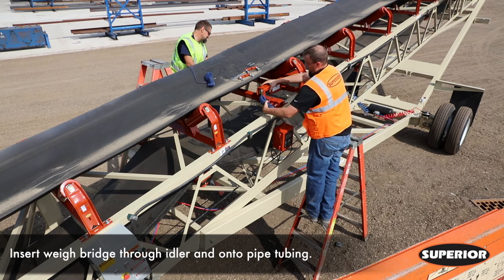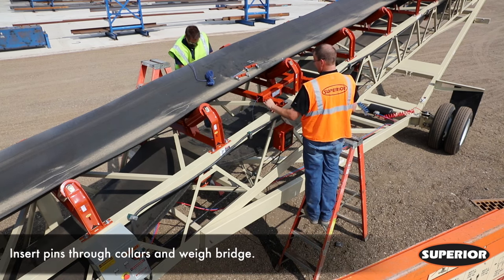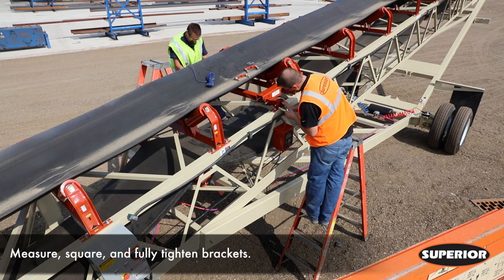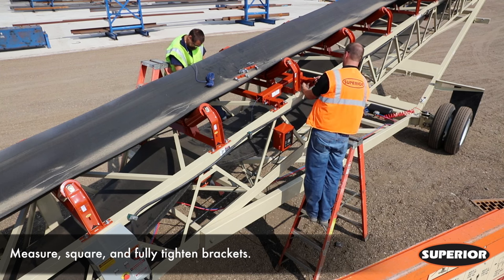Insert the weigh bridge through the center idler and onto the scale tubing. Ensure load cells are pointing towards the tail of the conveyor. Insert pins through collars and weigh bridge. Measure and square brackets. Once brackets are correctly positioned, fully tighten bracket bolts.